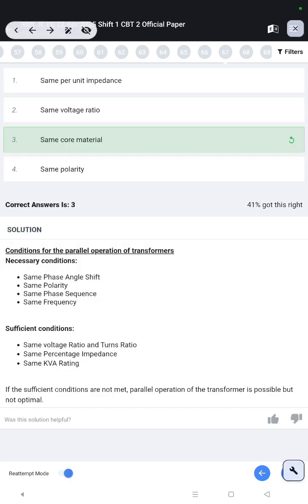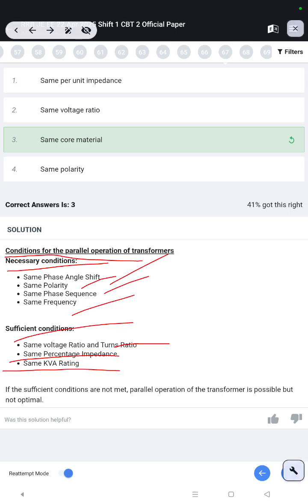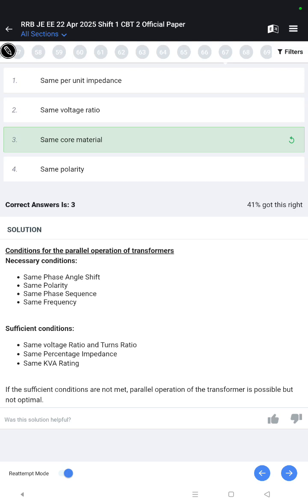Conditions for parallel operation of transformers. Necessary conditions: same phase angle shift, same polarity, same phase sequence, same frequency. Sufficient conditions: same voltage ratio and turns ratio, same percentage impedance, same kVA rating. If the sufficient conditions are not met, parallel operation of the transformers is possible but not optimal.